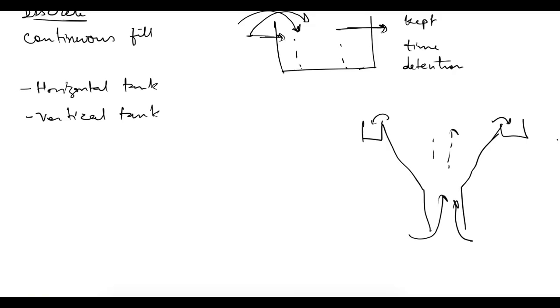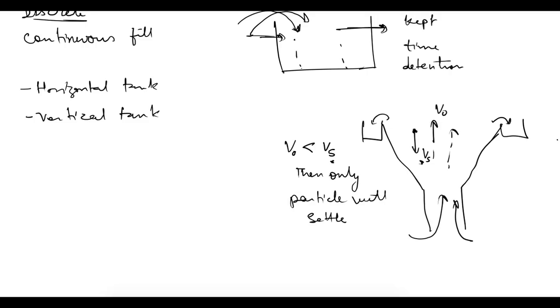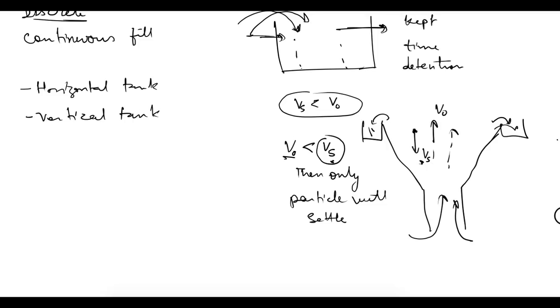As the water moves upward with velocity V₀, the velocity of settlement of particles is Vs downward due to gravity. In a vertical tank, the upward flow velocity must be less than the velocity of settlement for particles to settle. Particles with settling velocity less than V₀ will simply flow out with the water and not settle. In the horizontal tank, the theory is different.